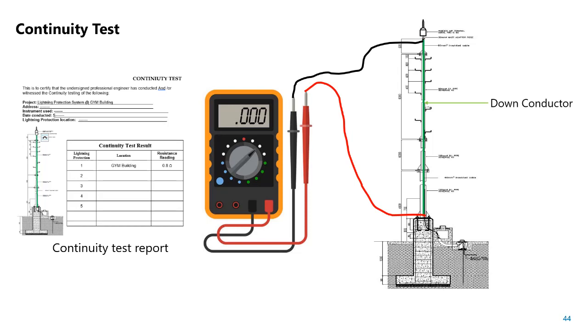So that's another reason. Specifically, if the device is new, yes, we still do a continuity test as a formality. But as practicing engineers, we all know that if it is new, then it has definite continuity. But for an existing one, you should do a continuity test.